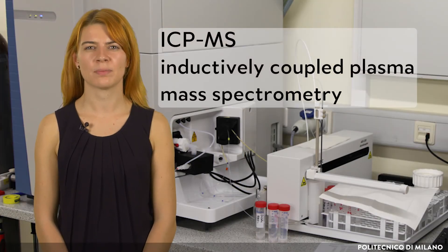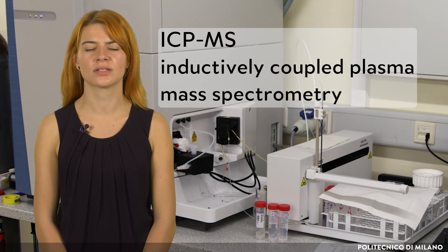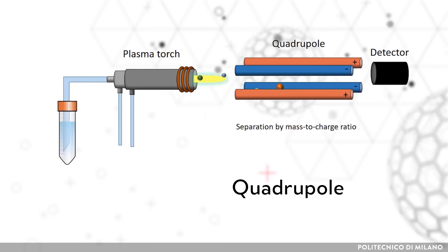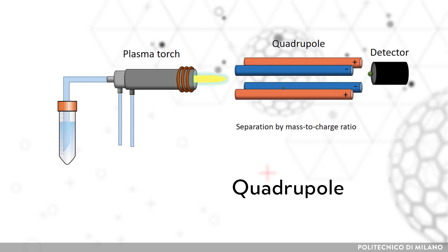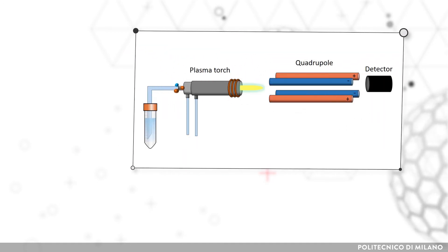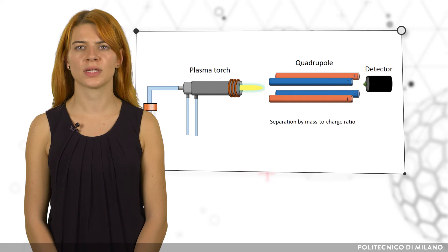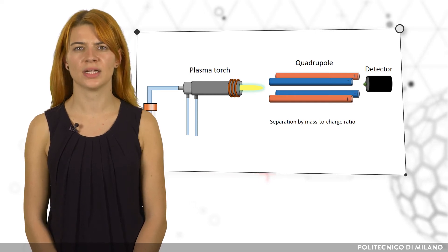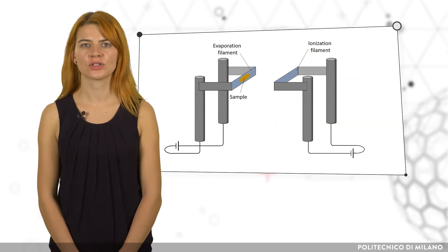For inductively coupled plasma mass spectrometry (ICP-MS), the sample has to be dissolved so that a diluted solution can be atomized and ionized in the plasma. Often, a quadrupole mass analyzer is used for mass separation. By applying oscillating electric fields to four cylindrical electrodes, only ions with a certain mass-to-charge ratio can pass the quadrupole on stable trajectories. ICP combined with a quadrupole mass analyzer offers a robust tool for sensitive quantification of elemental composition as well as precise quantification of trace elements.